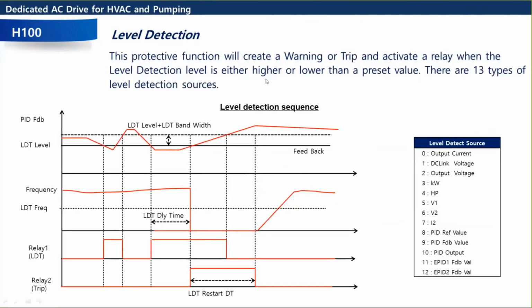All right, so a few more functions here that you may run into. Level detection. Again, this level detection is typically used with PID as well. So you could set a high or a low level detection based on a preset. And there's 13 different ones you could select from. On the right here, you could do just current level detection. You could do it based on voltages, kilowatts, horsepower, V1, V2, I2, which are analog inputs. Or you can do it based on feedback, which I think would be most common. So if you hit a low pressure or a high pressure PSI, then you could trip the drive out.